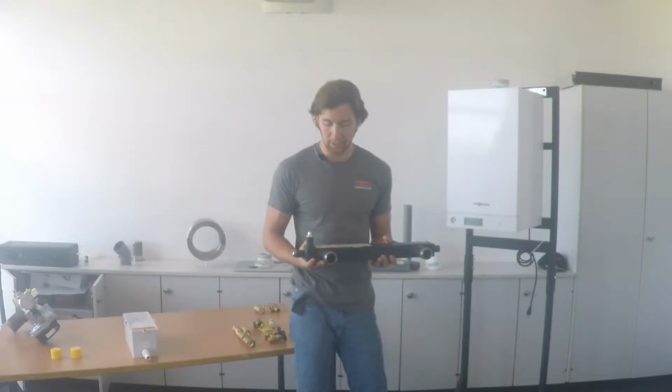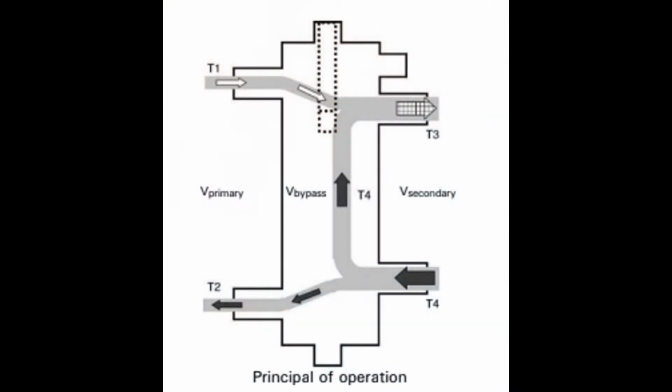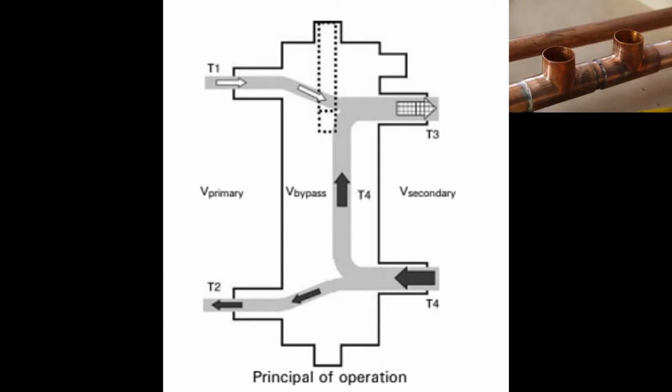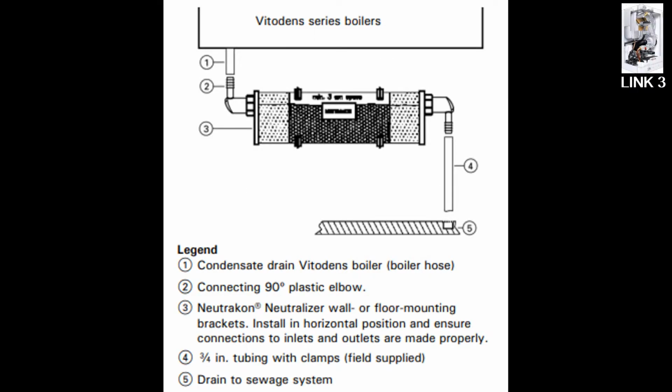We recommend using a low loss header, which you can pick up at your wholesaler, but you can also achieve the hydraulic separation by installing closely spaced T's into the plumbing just before connecting into the house line. Along with your low loss header, we also recommend getting one of the condensate neutralizing boxes at your wholesaler.